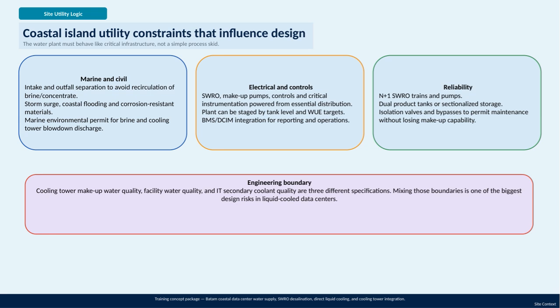Storm surge and coastal flooding are real concerns, so we use corrosion-resistant materials to handle these harsh conditions. Additionally, obtaining marine environmental permits is essential to regulate the discharge of brine and blowdown water from the cooling towers. On the electrical and control side, all key components like the SWRO units, makeup pumps, and critical instrumentation must be powered from essential power distribution to ensure continuous operation.